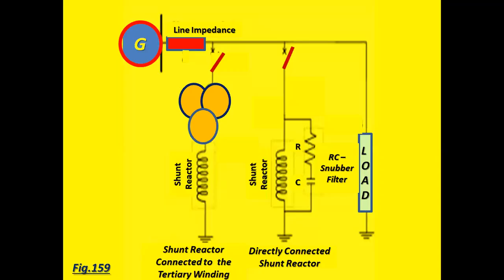See the diagram. Power generation, generating unit, line impedance, shunt reactor connected to the tertiary winding of the transformer or directly connected to the system, shunt reactor, load. One filter circuit is there, the RC snubber filter.